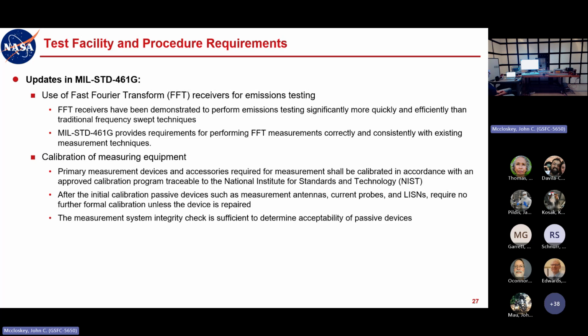With all of that, the measurement system integrity check, which you should perform before every test, is sufficient to determine the acceptability of passive devices. That's when you're putting a known signal in. We'll talk about that here, I have a chart on that a little bit later. You put a known signal into the measurement system, verify that what you're getting out is the expected value, and it's pretty generous, plus or minus 3 dB. That's the world we live in, right?